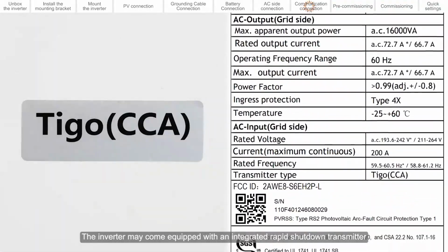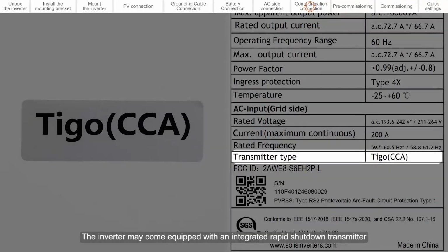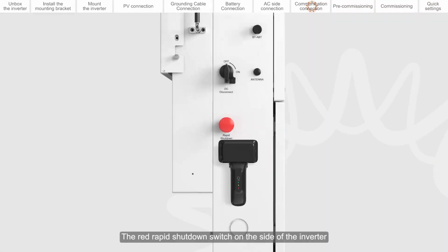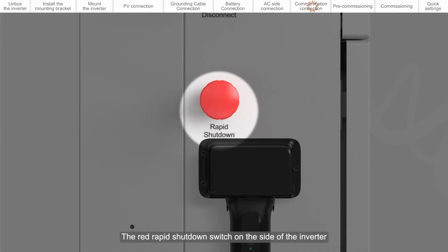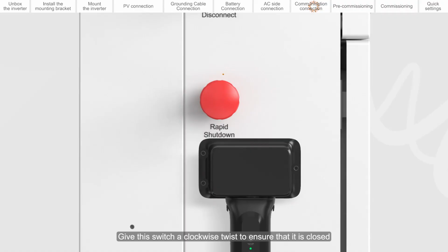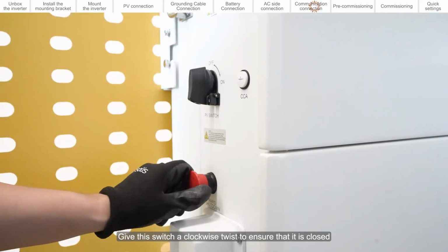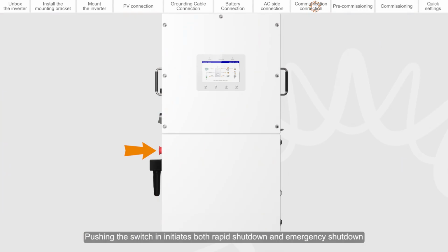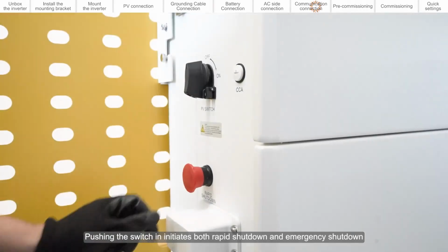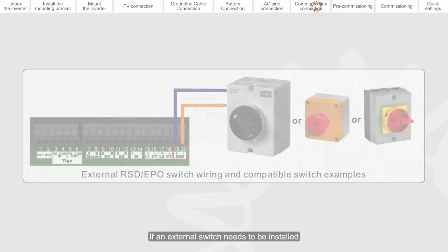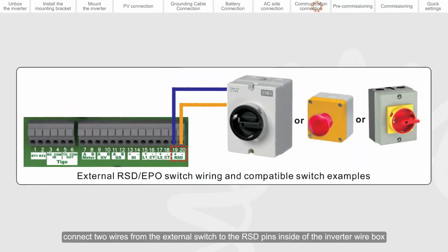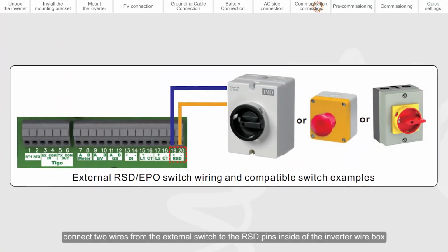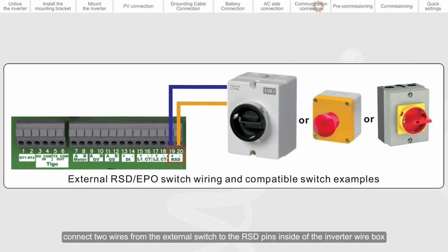The inverter may come equipped with an integrated rapid shutdown transmitter. Check the specification label of the inverter to see if it has a transmitter and what kind it is. The red rapid shutdown switch on the side of the inverter will shut down the inverter and disable the internal transmitter. Give this switch a clockwise twist to ensure that it is closed. Pushing the switch in initiates both rapid shutdown and emergency shutdown. If an external switch needs to be installed, connect two wires from the external switch to the RSD pins inside of the inverter wire box.